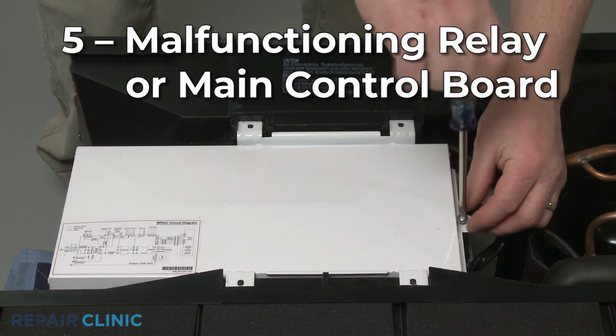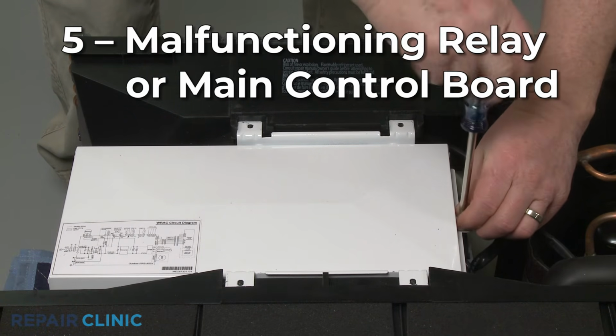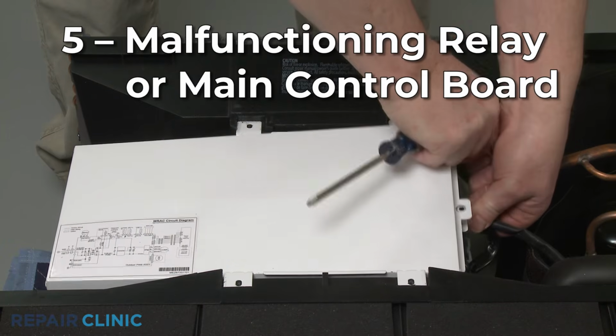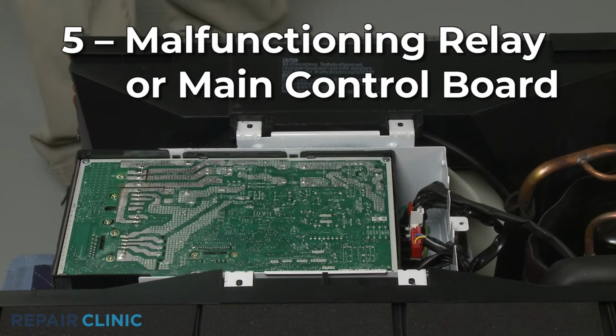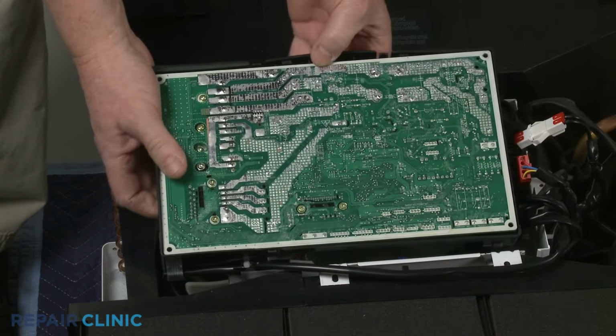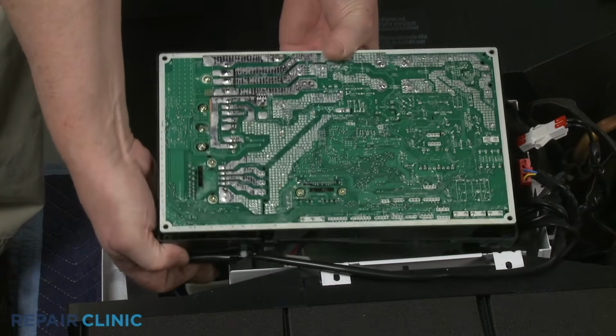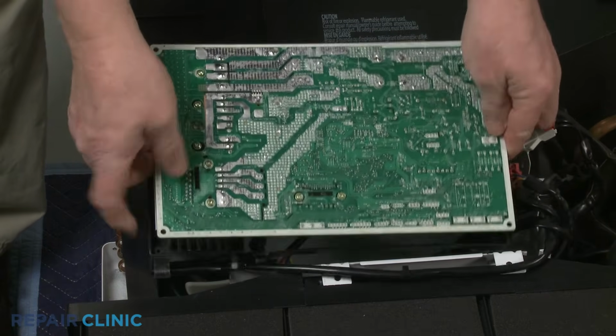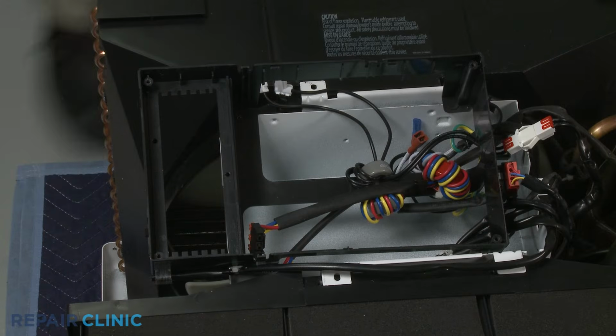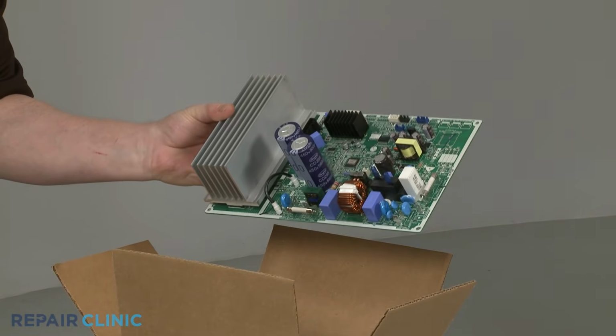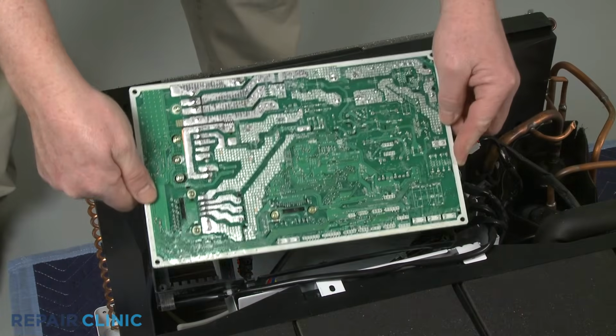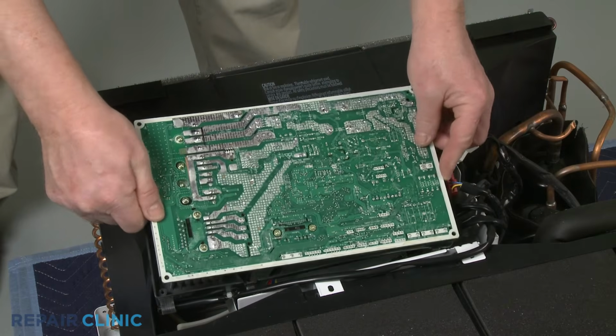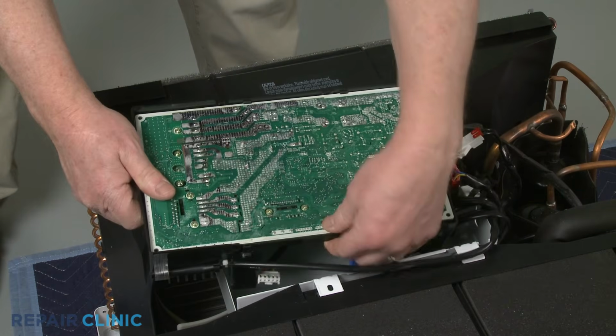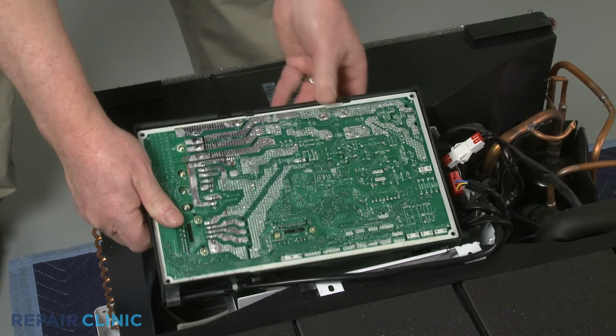Relay boards and main control boards provide voltage to many of the air conditioner's components, including the fan motor. If the board is malfunctioning, the fan motor may not be receiving voltage. Since this is not that common of a problem, you should verify the other more likely defective parts are working properly before considering a relay or main control board replacement.